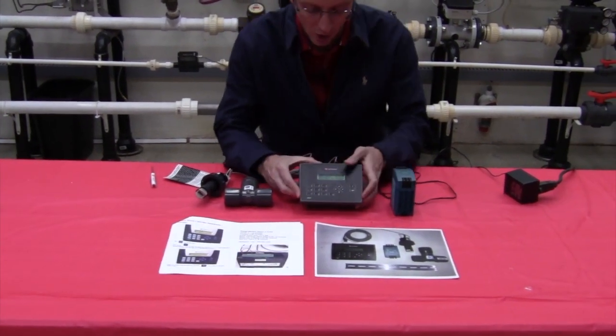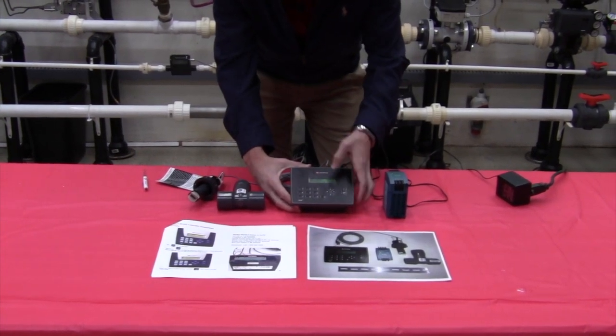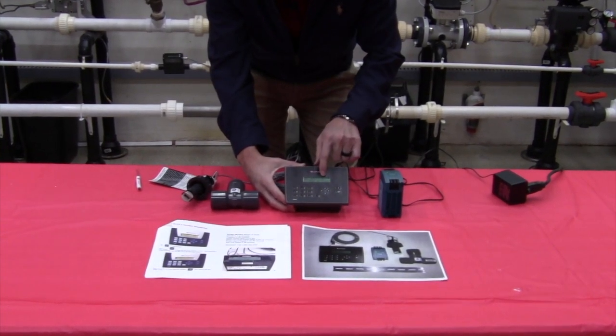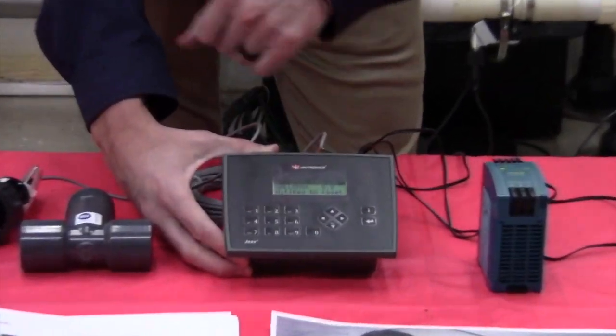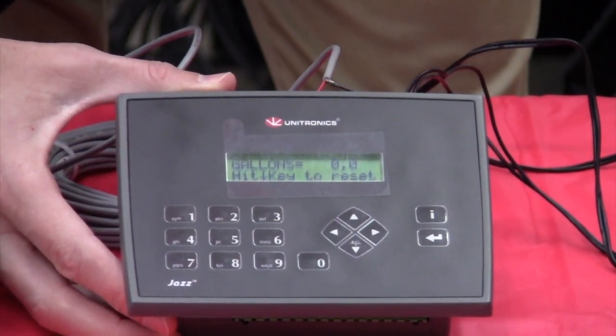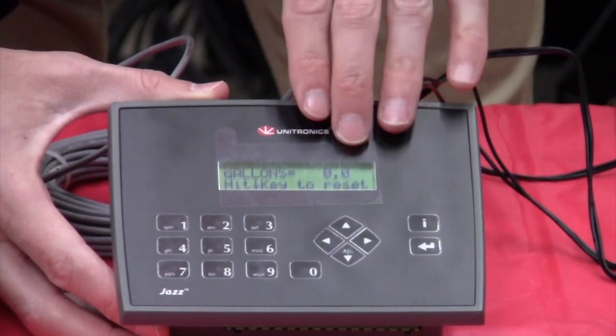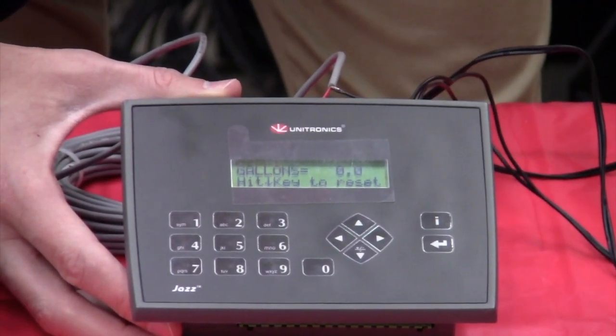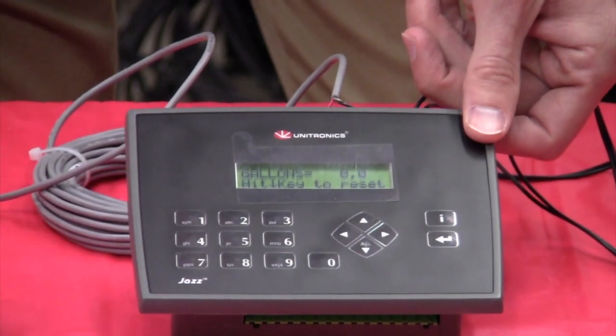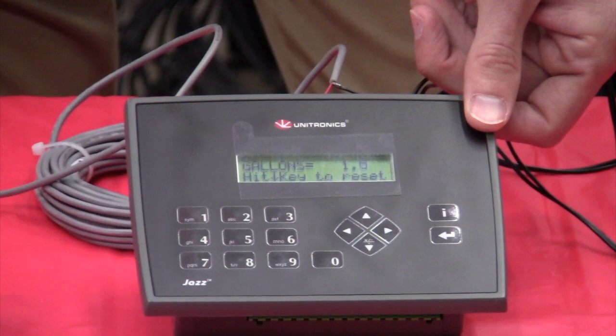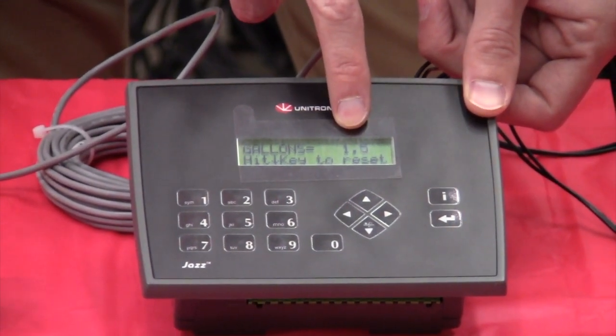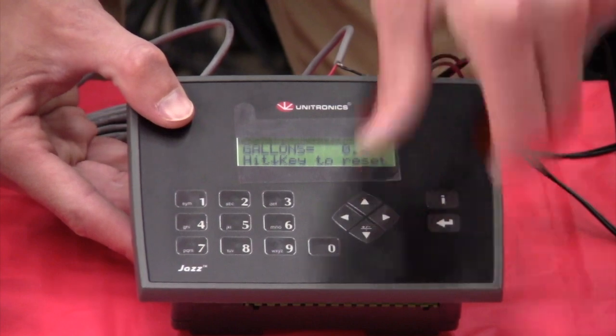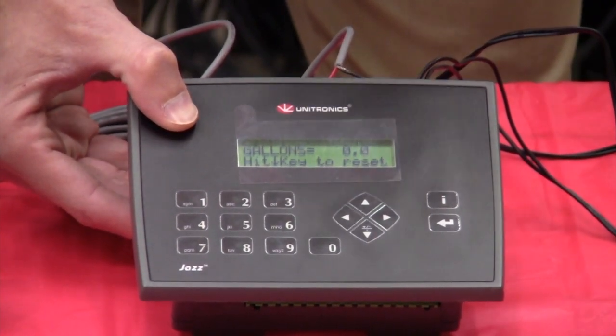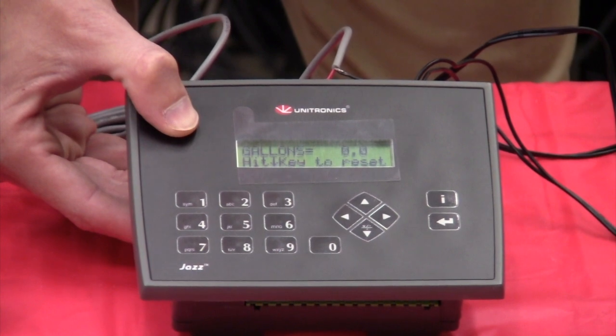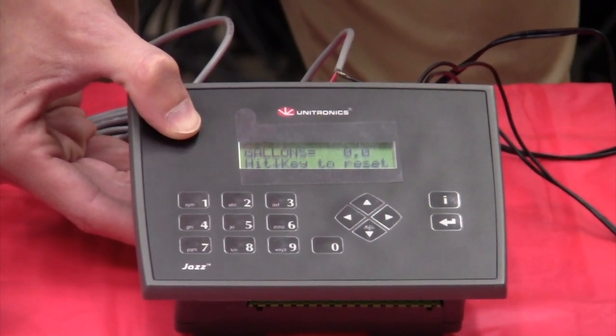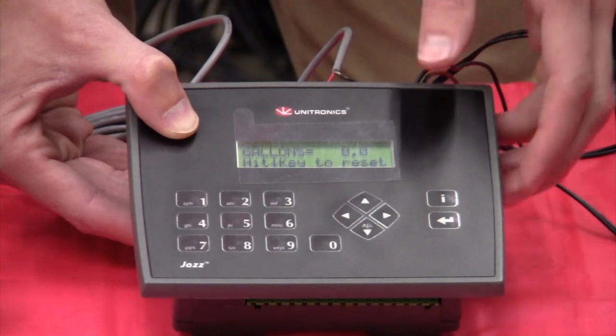Now if we look at the display, right from the front screen, we show you gallons, we give you a readout, and then it says hit the I key to reset. So from inside the store, the cashiers can see the flow and reset it after each customer. If I give this paddle a spin, you will see it totalize on the screen. If I simply hit the down arrow, it will reset back to 0. After each customer is done filling jugs, you can figure out how many jugs or total gallons they filled, and then reset it before the next customer begins.